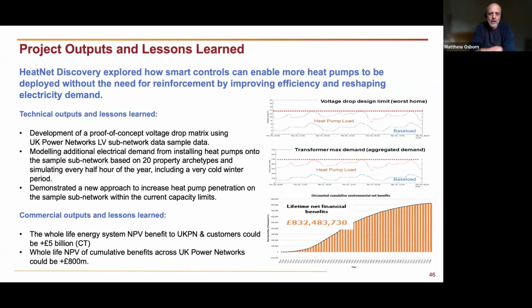So what did we learn? HeatNet Discovery explored how smart controls can help install more heat pumps on a low voltage network without extra reinforcement, by reshaping electricity demand and improving overall heat pump efficiency. We developed a proof of concept voltage drop matrix using UKPN's sub-network data, and modeled electrical demand for installing increasing numbers of heat pumps onto that sample network, simulating power demands for every half hour over the year during a cold winter. Finally, we demonstrated a new way to increase heat pump penetration on that sample network within current design limits.